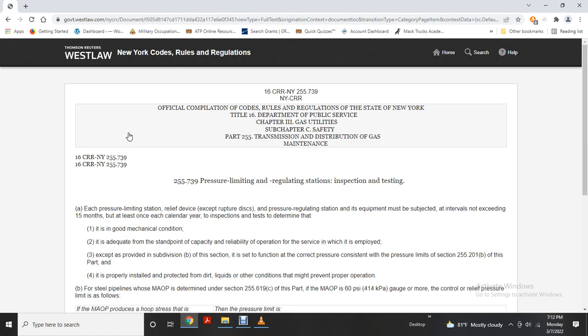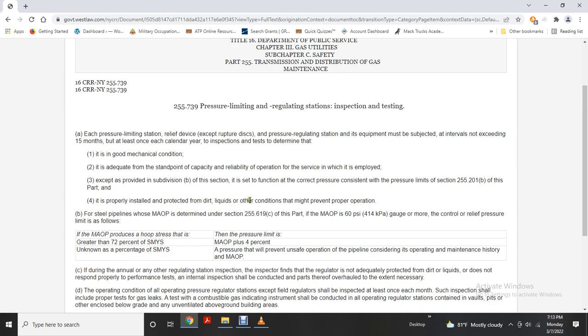Pressure limiting and regulating station inspection and testing. Each pressure limiting station, relief device except rupture discs, and pressure regulating station equipment must be subject to inspection and testing at intervals not exceeding 15 months, at least once each calendar year, to determine that it is in good mechanical condition, has adequate capacity at the set point, and is reliable in operation. Except as provided in subdivision B of this section, the set pressure must function correctly and be consistent with the pressure limits of section 255-201B of this part. The equipment must be properly installed and protected from dirt, liquids, or other conditions that might prevent proper operation.